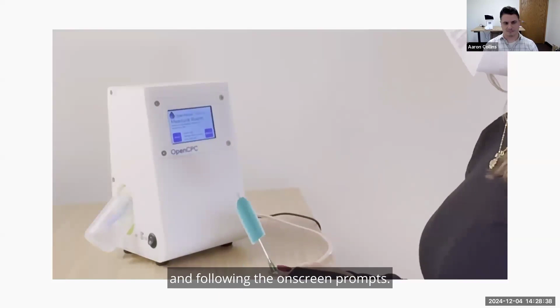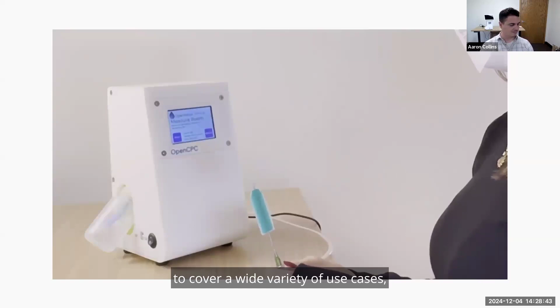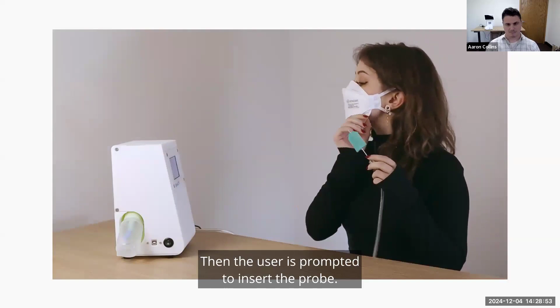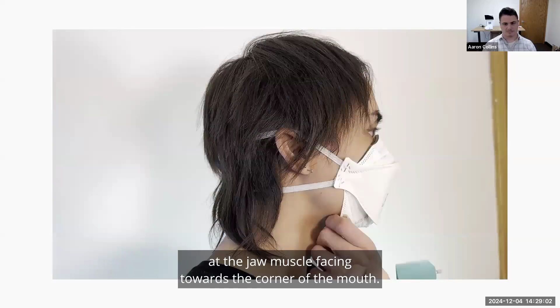The user starts the test by pressing the Start button and following the on-screen prompts. All measurement links are software configurable to cover a wide variety of use cases, including compatibility with ANSI standard Z88.10. OpenFit measures the ambient concentration of the particles in the occupied space. Then, the user is prompted to insert the probe. The user places the probe between their face and the respirator. We recommend placing the probe at the jaw muscle, facing towards the corner of the mouth.